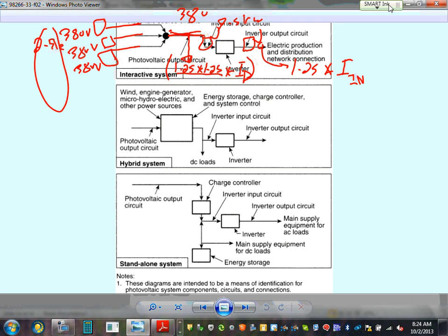If you have a short circuit, and you take the positive and negative of one panel and short them together, it's supposed to be sized to sit like that forever, and the conductors will not burn. They just keep carrying the electricity in the conductors. The conductors get hot, but they don't burn. That's what sizing these conductors is. Same thing for the string, one panel or multiple panels.